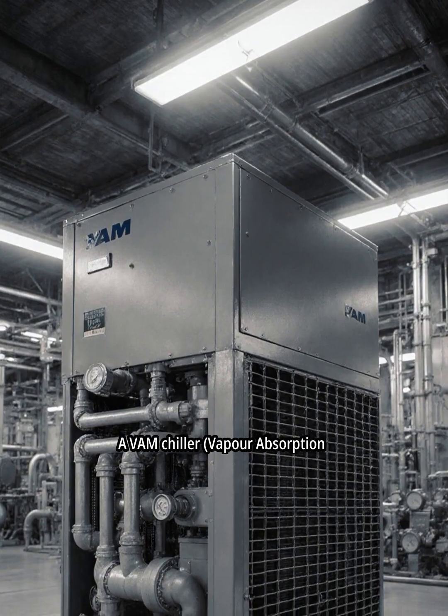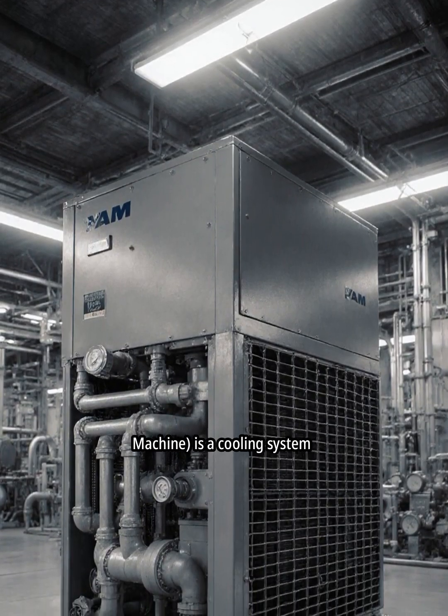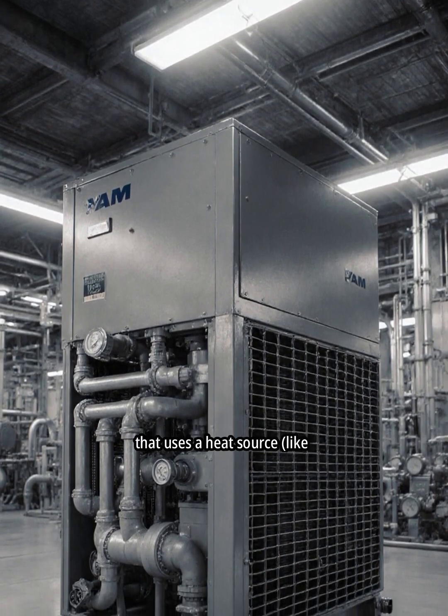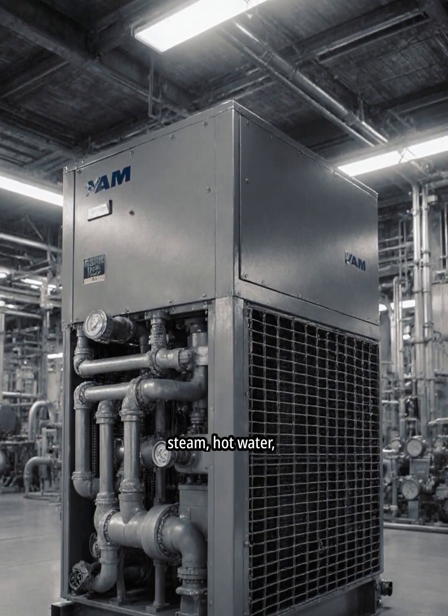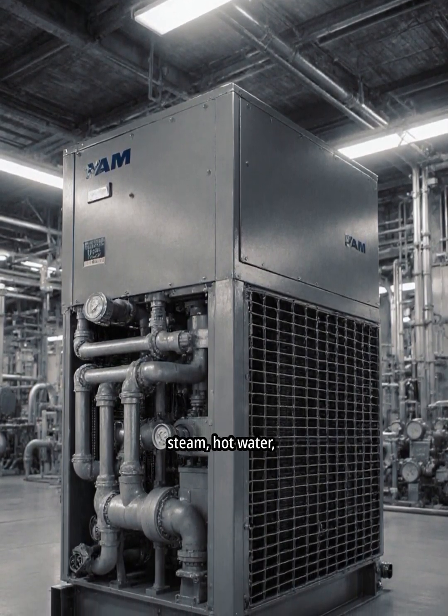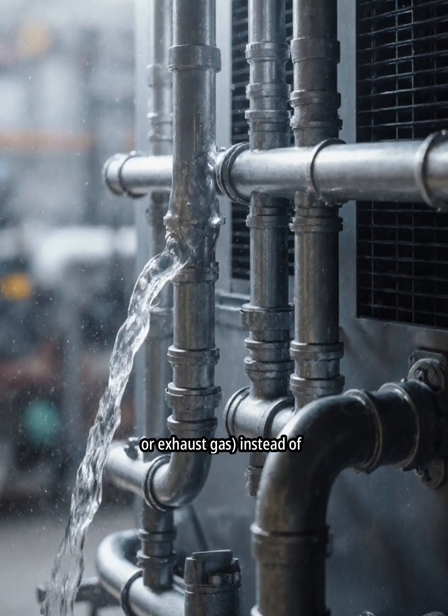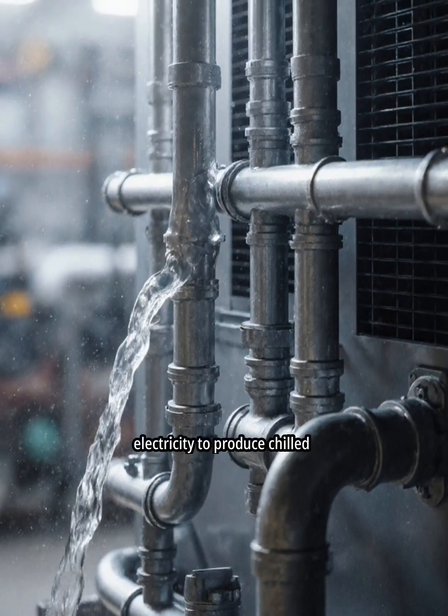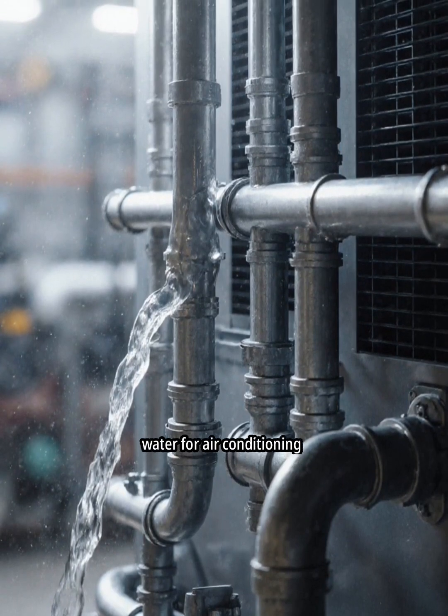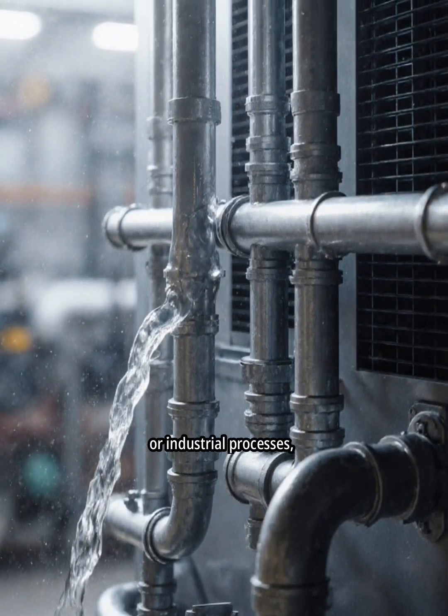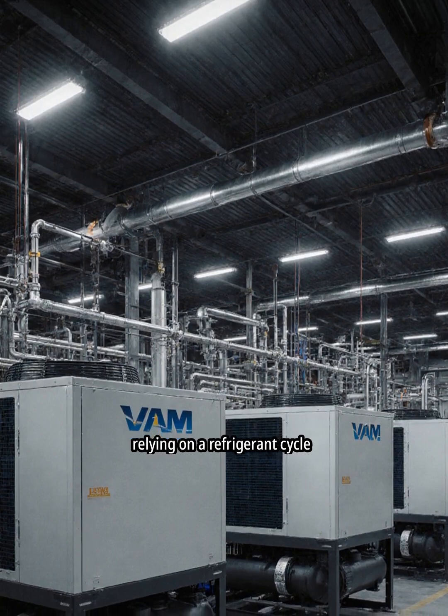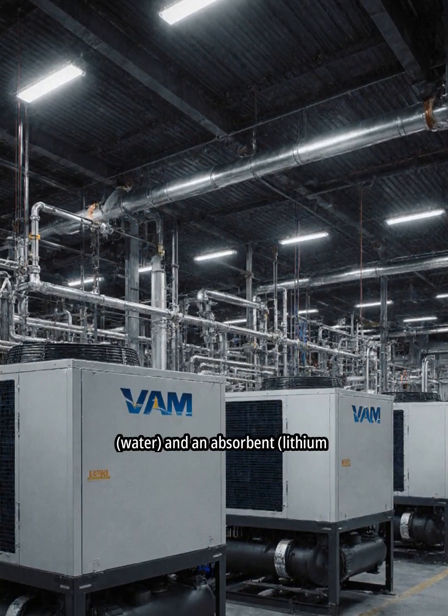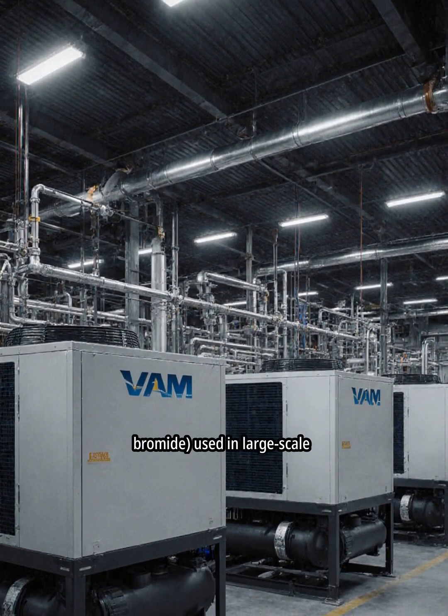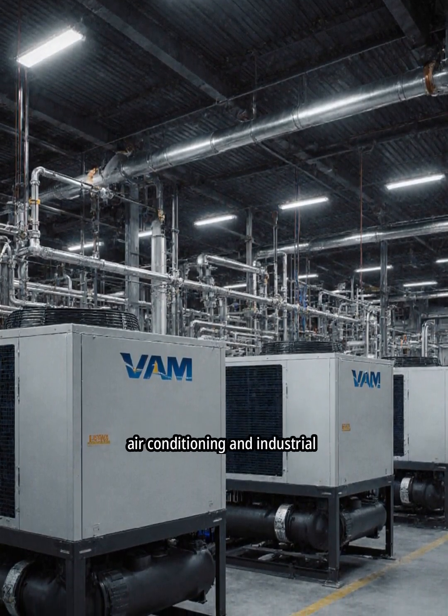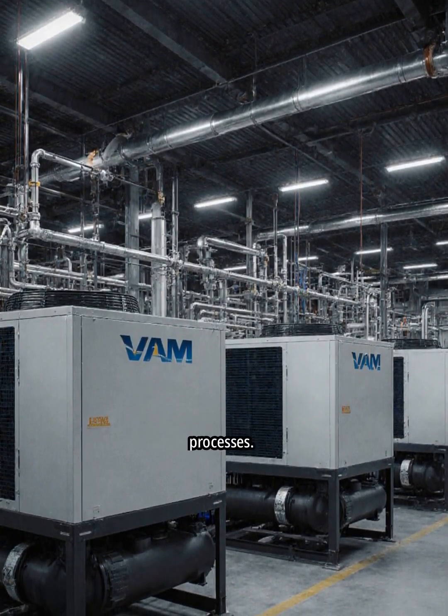A VAM chiller, vapor absorption machine, is a cooling system that uses a heat source, like steam, hot water, or exhaust gas, instead of electricity to produce chilled water for air conditioning or industrial processes, relying on a refrigerant cycle, water, and an absorbent, lithium bromide, used in large-scale air conditioning and industrial processes.